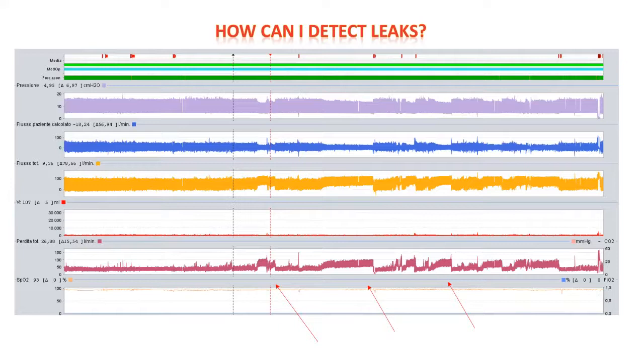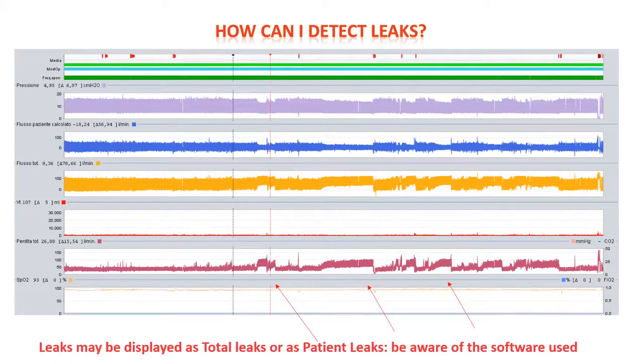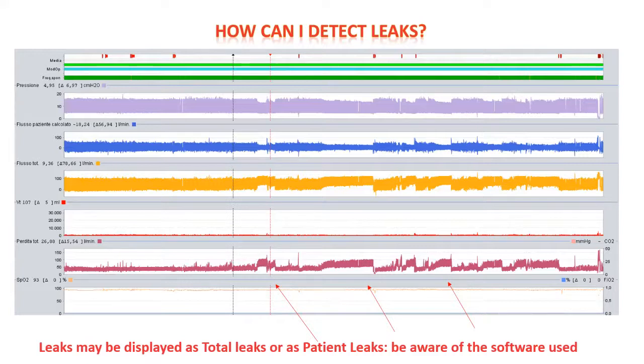How can I detect leaks? If you look at detailed data, all software give you the possibility to look at a trend of leaks. The important thing is to know which software you are using and what kind of leaks it shows. In some software — like Breas — you have so-called 'total leaks,' meaning intentional leaks (the leaks around the mask holes) plus non-intentional patient leaks around the mask. In other software, you have only the non-intentional leaks.